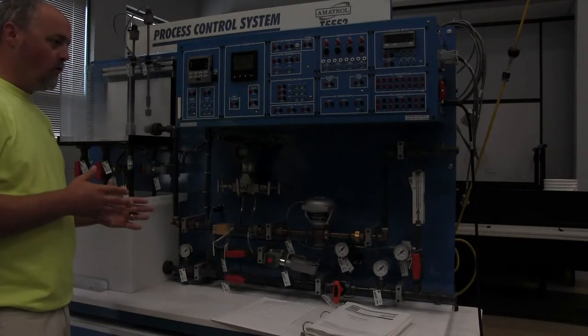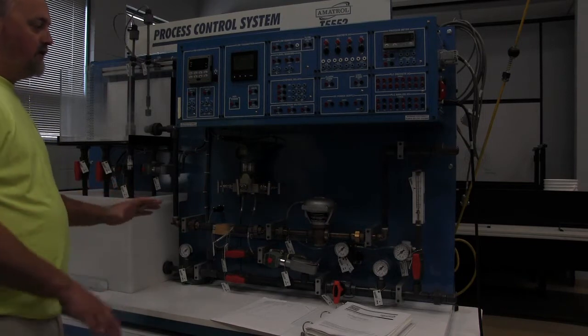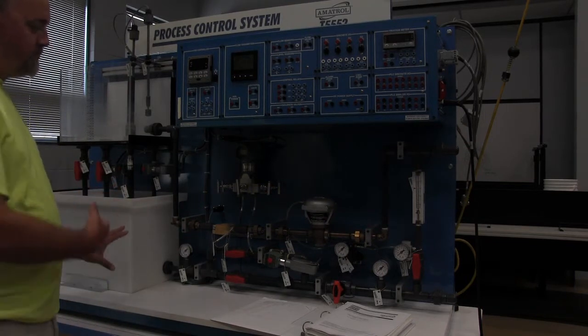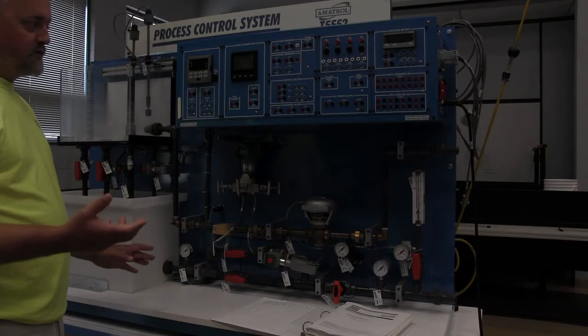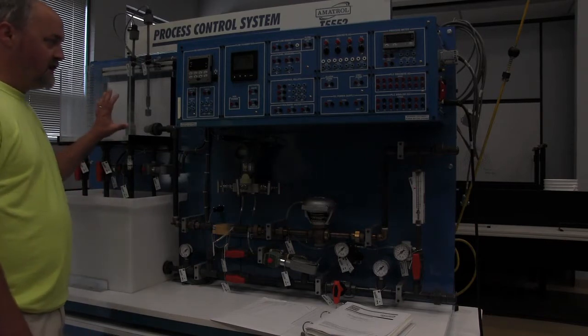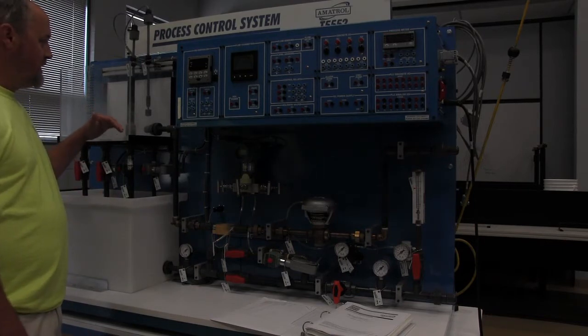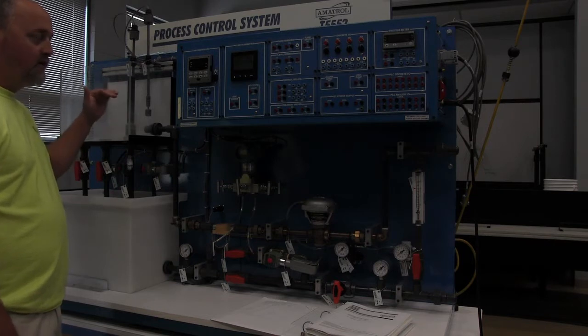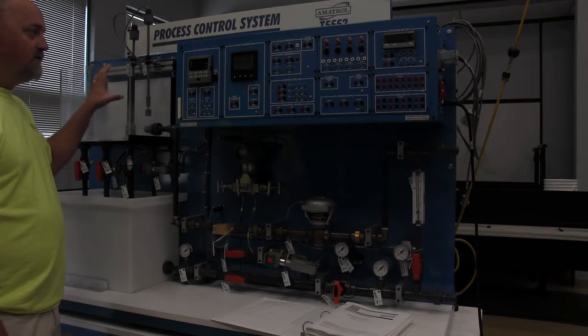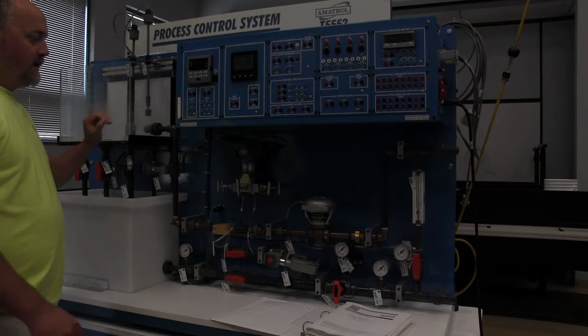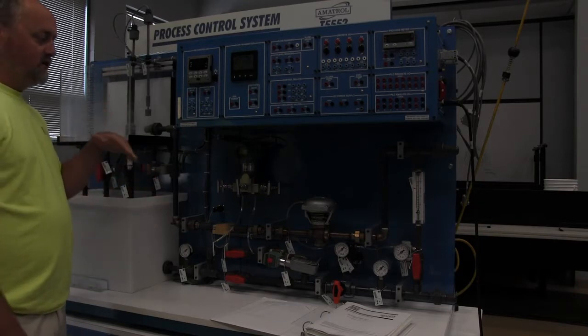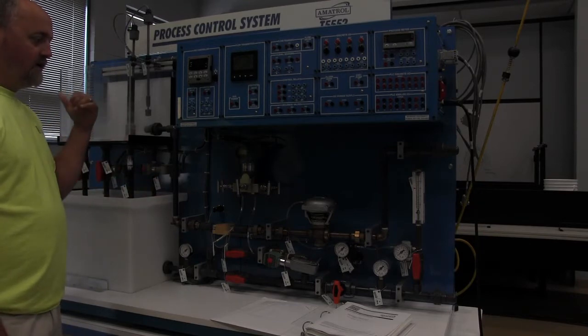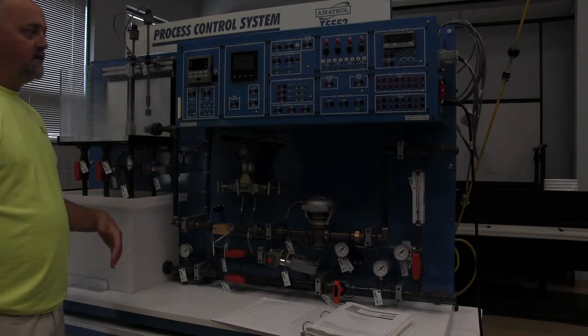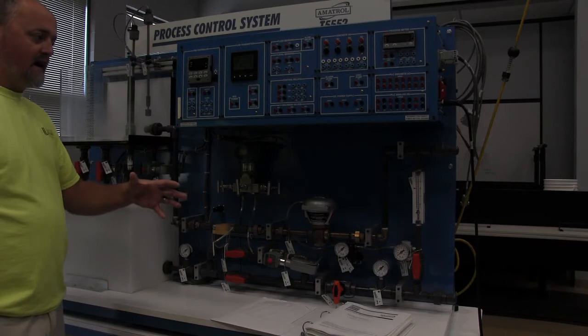And this is a basic, in my opinion, this is a basic water plant. You have water in an aquifer. You're pulling water out of it. You're either treating it or putting it in a storage tank. You're running the storage tank based off of either a level with floats or with a transducer. You have flow meters. You will start it, stop it, add chemicals if needed, treat the water, whatever is needed, and then you send it back out.